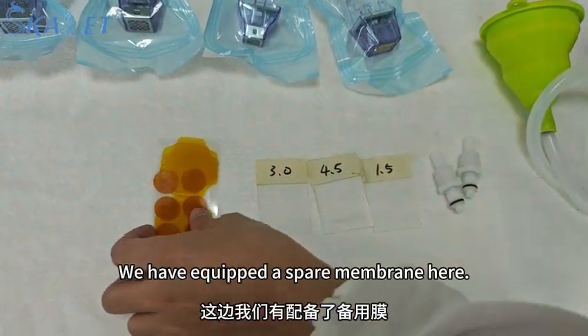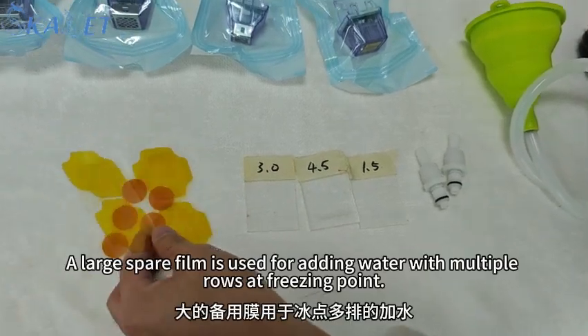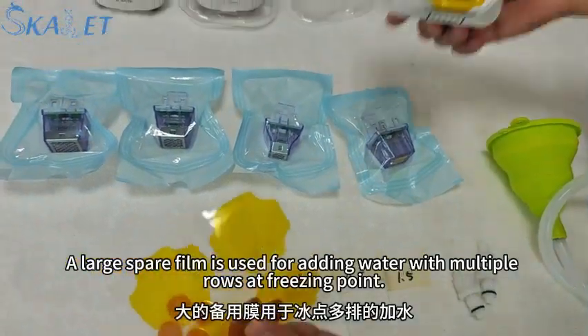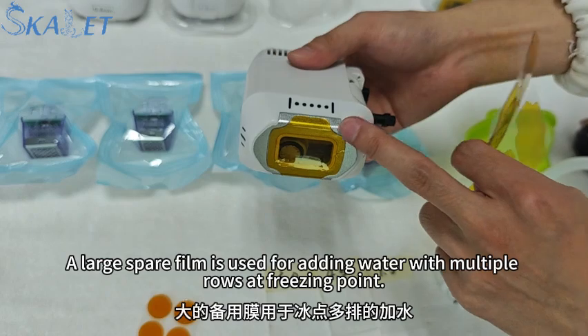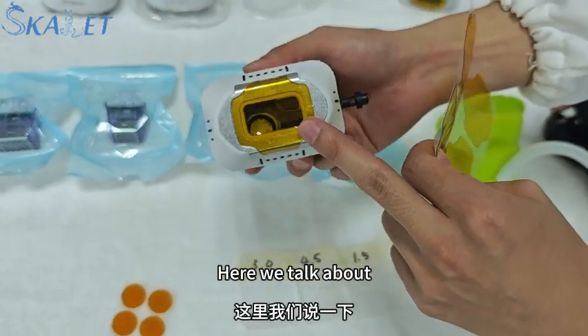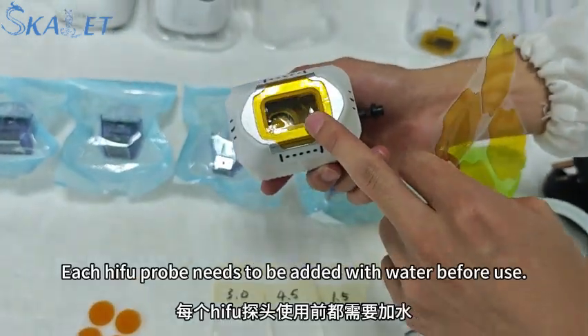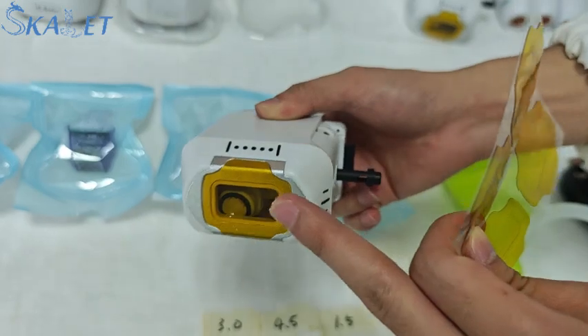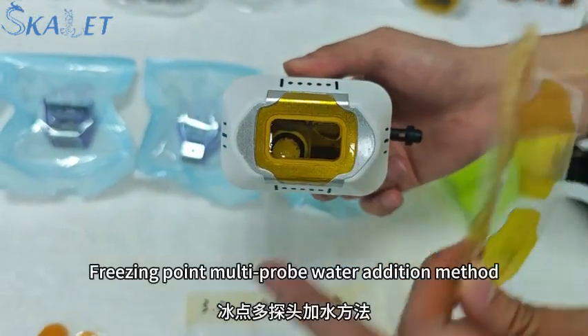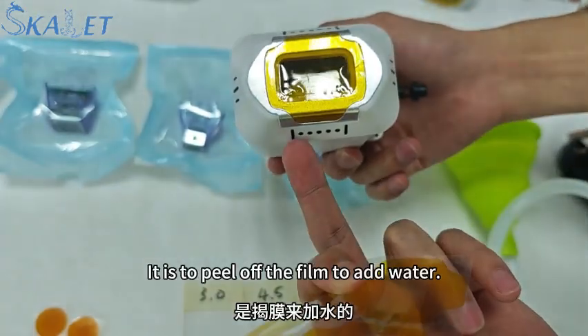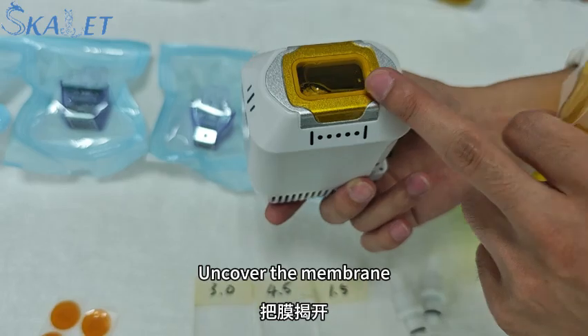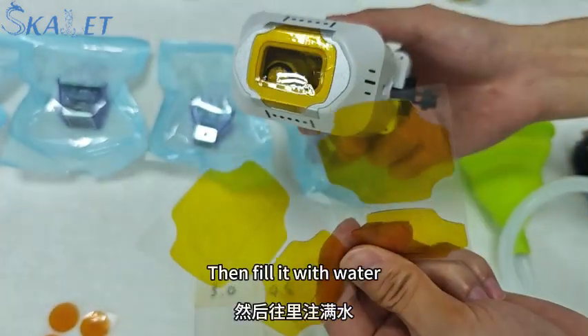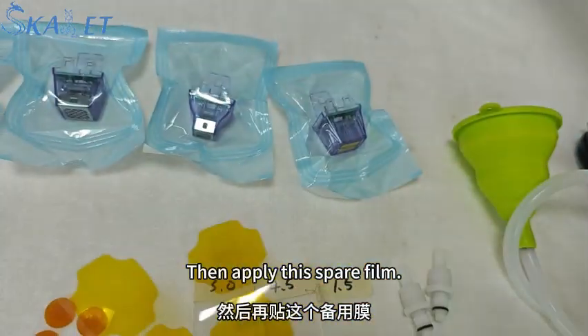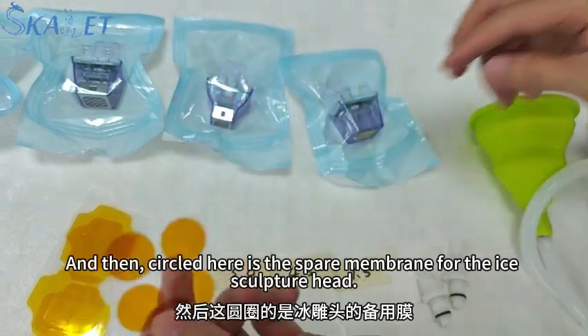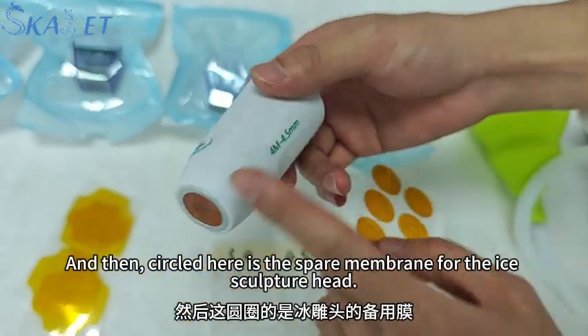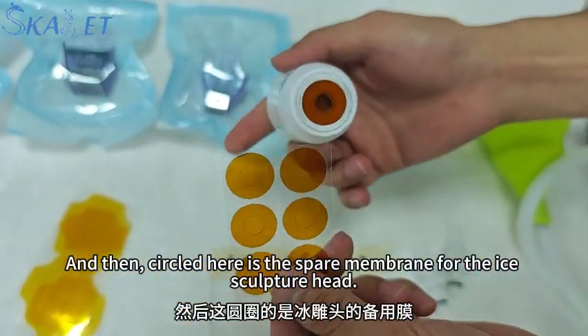We have equipped a spare membrane here. A large spare film is used for adding water with multiple rows at freezing point. Here we talk about each HIFU probe needs to be added with water before use. Freezing point multi-probe water addition method: peel off the film to add water, uncover the membrane, then fill it with water, then apply this spare film. And then, circled here is the spare membrane for the ice sculpture head.